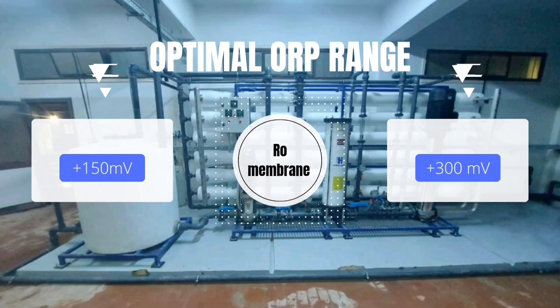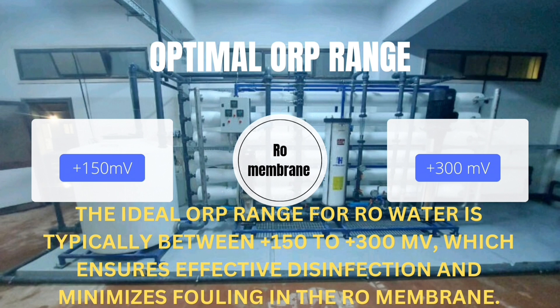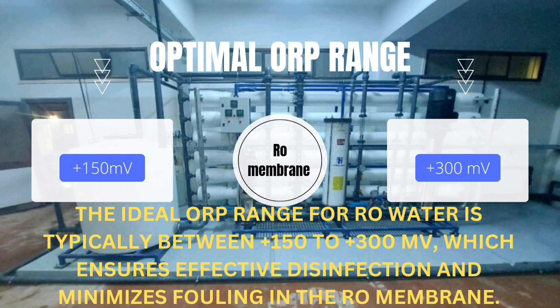Optimal ORP Range: The ideal ORP range for RO water is typically between +150 to +300 mV, which ensures effective disinfection and minimizes fouling in the RO membrane.